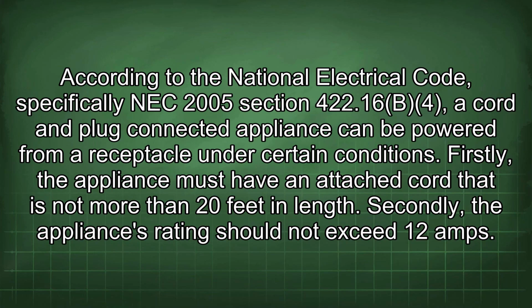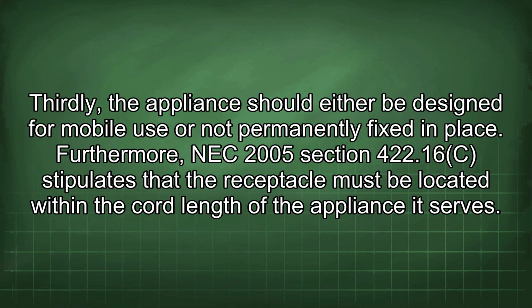According to the National Electrical Code, specifically NEC 2005 Section 422.16b4, a cord and plug connected appliance can be powered from a receptacle under certain conditions. Firstly, the appliance must have an attached cord that is not more than 20 feet in length. Secondly, the appliance's rating should not exceed 12 amps. Thirdly, the appliance should either be designed for mobile use or not permanently fixed in place.